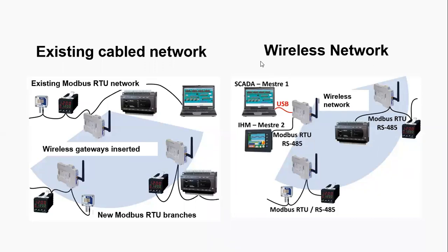If my master is TCP IP Modbus and my slave is RTU, can I use a serial to Ethernet converter? Yes, you can.